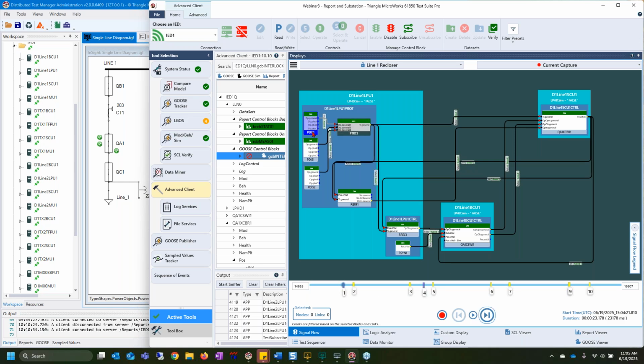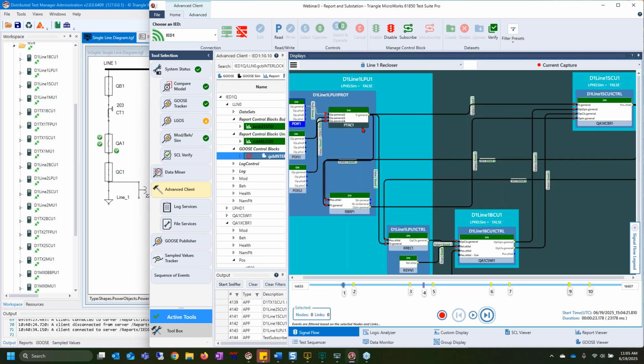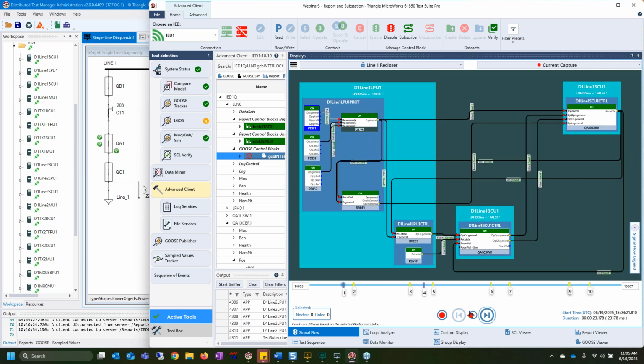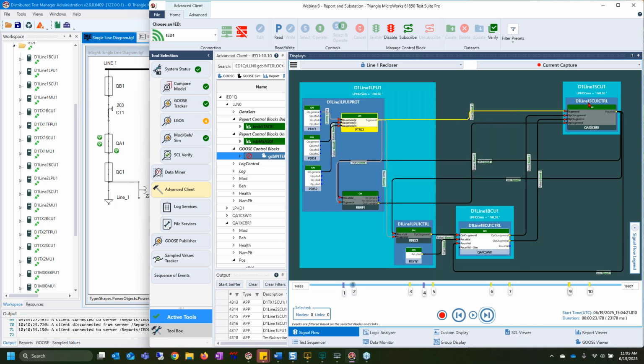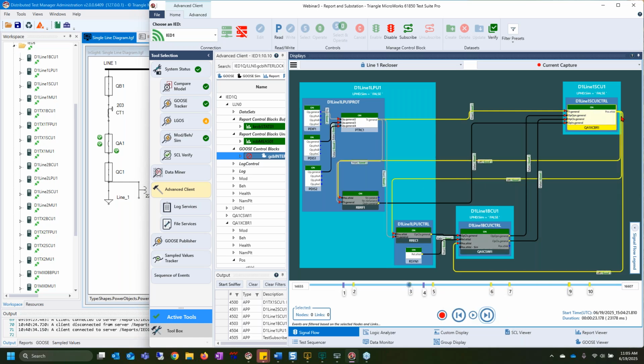We'll see a differential fault is detected, which gets sent to the PTRC, which is effectively multiplexing all possible fault entries into it. And then the output of that will be this trip.general. The next step, we can see it's a yellow marker on this line. You can see the yellow line here is now GOOSING out. So the LPU here is issuing a GOOSE message out to the SCU, which is receiving the trip general, and that's going to trip the breaker, which is why the breaker opened. And when the breaker opened, its database updated. When it's database updated, it then needed to send a GOOSE message out, and that is being delivered to our LPU and our BCU, or our bay controller unit here.